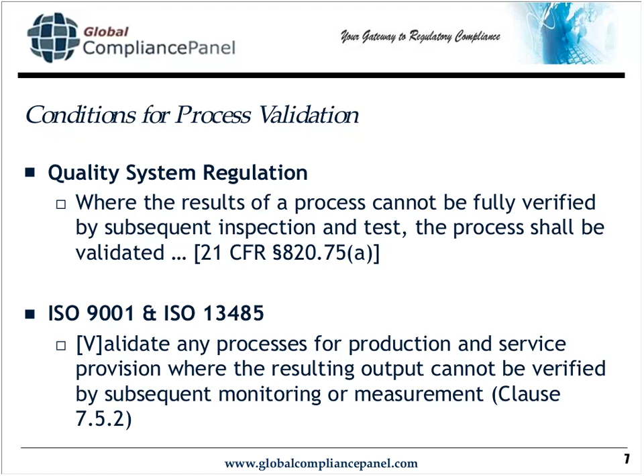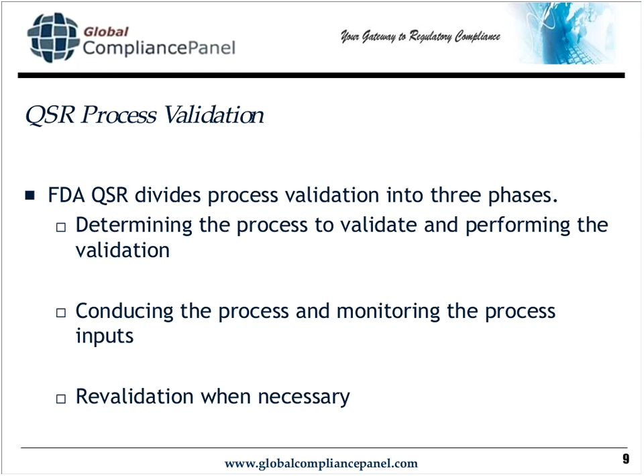Now, let's look at the requirements in QSR explicitly. FDA QSR divides process validation up into 3 phases, and this is going to be a very important model for us here. So the first phase is how do we determine what processes to validate, and how do we actually perform the validation? So this is 820.75(a), and we'll look at it in detail in a moment. The second piece is now that we've got the process validated, how do we actually run it? Right? So the issues involving running of the process, monitoring the process inputs. And then the third phase is when we have to revalidate. So there are a set of conditions, and if we meet those conditions, then we have got to do something about revalidation of the process and leave some records behind. So we'll look at what's going on there as well.